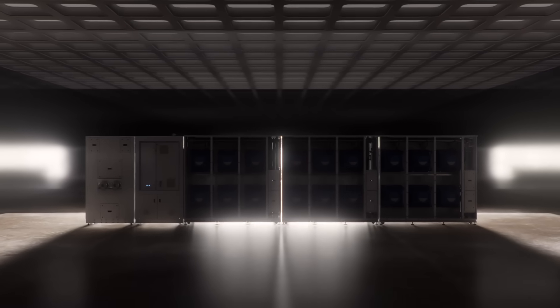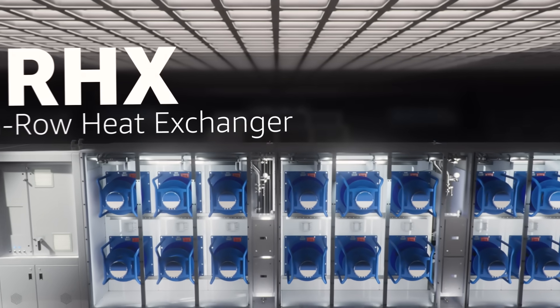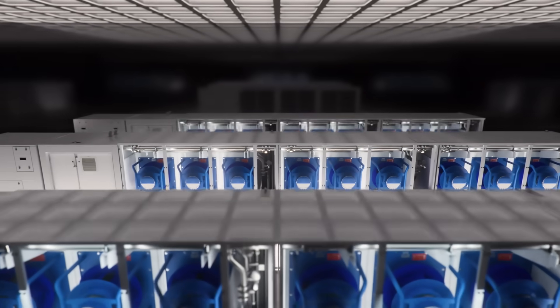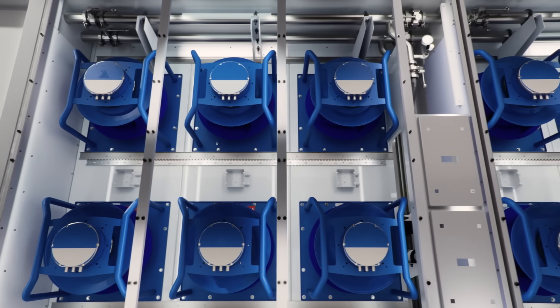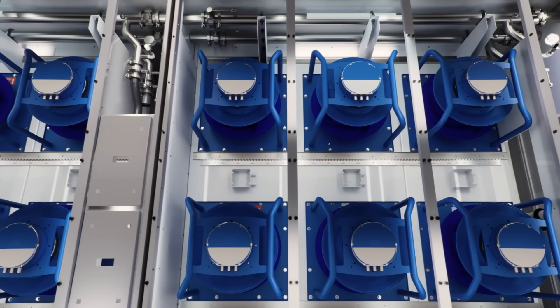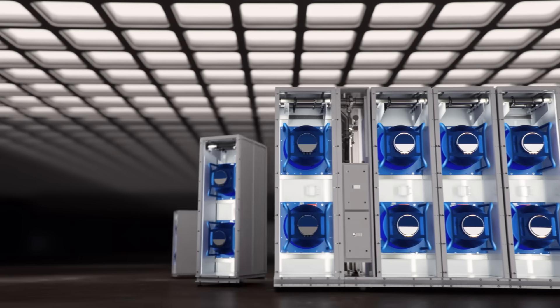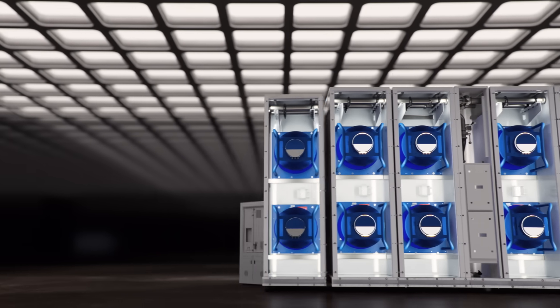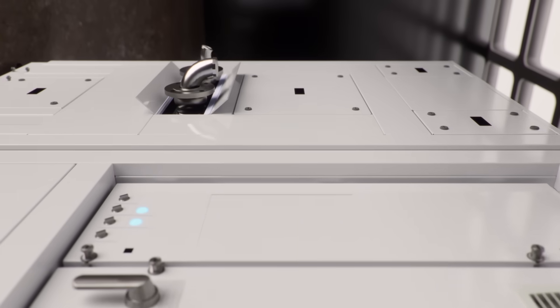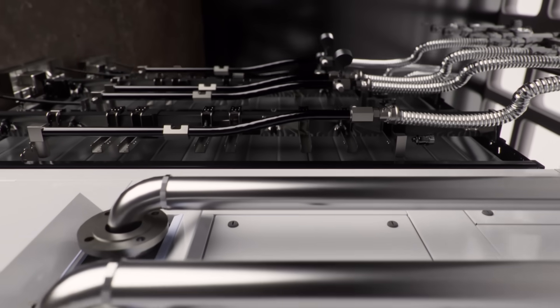So we did what we often do at AWS — we invented our own solution to have the best of both worlds. This is the in-row heat exchanger, or IRHX as we call it. The IRHX is an Amazon-designed liquid cooling system. It can be installed with no changes to the air-cooled mechanical design and minimal changes to existing infrastructure, meaning it can be deployed in existing data centers as well as new builds. The IRHX was designed to allow us to scale fast, standardizing our equipment and supply chain, built to spec for our standard rack dimensions to fit within our existing data centers.